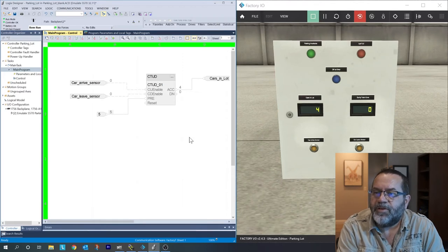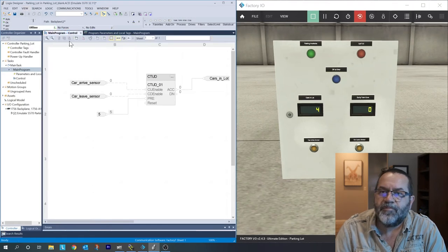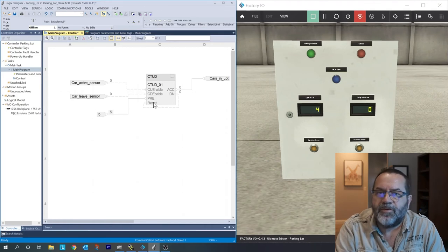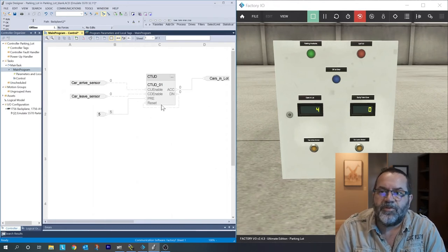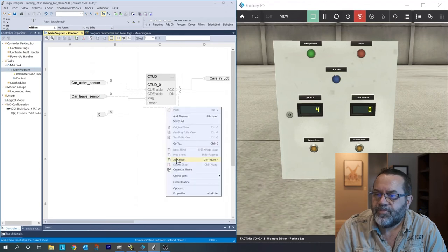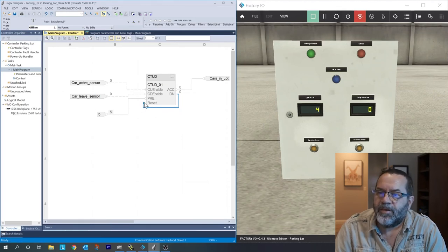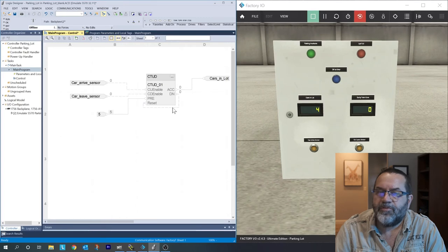That's how easy it is with function block diagram — it's very different from ladder logic. Best thing to do is think about what you need to accomplish and then put in the blocks you need. A couple of tricks with function block: if I have this done bit reset my counter, I've created a loop and function block isn't going to know where to start when it begins scanning. So anytime I have a loop I have to tell it where to start — I right-click on the dotted line and select 'assume data available.' That's just a fancy way of saying 'start here.' That gives me a little double-arrow there and everything's going to be good.